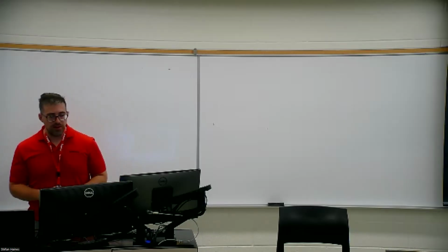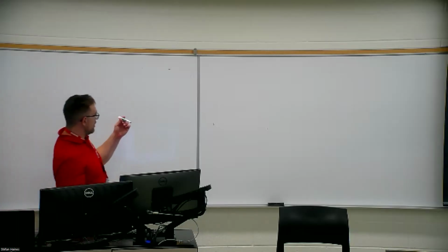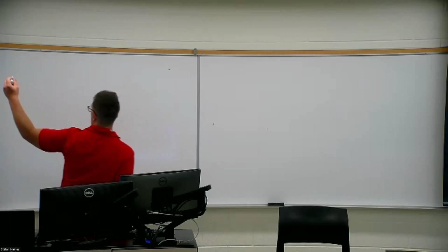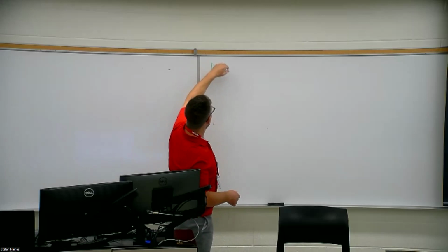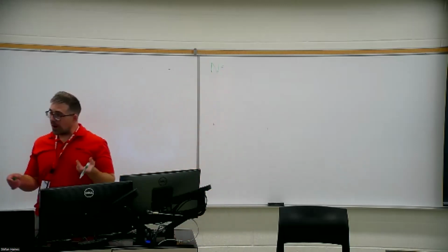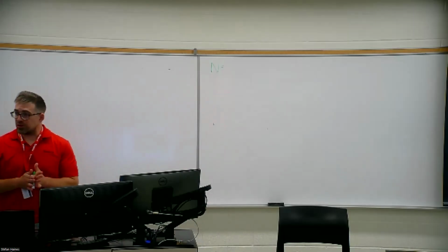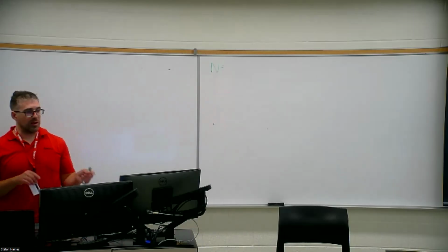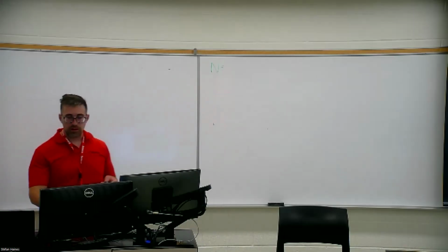So the first formula is your plate count and your plate efficiency. I'll put them all on the board one at a time here, because there are 4 of them, all with very minor differences. They should all be around the same number. I'm not sure which one of the formulas your machine will choose when you're running HPLC. It will probably choose the most consistent one, I guess you could say. As long as all your peaks are measured the same way, everything should be relatively fine within a couple percent.